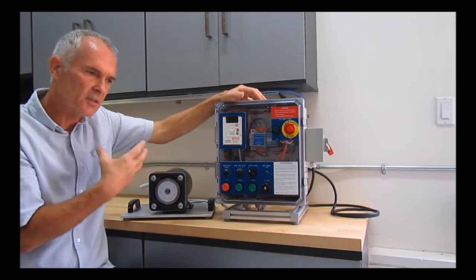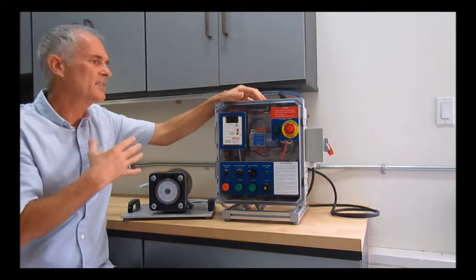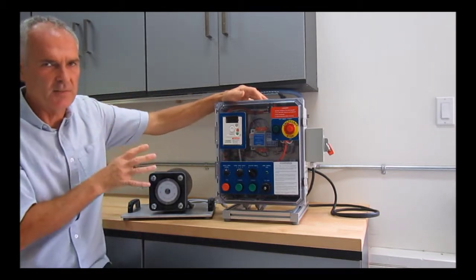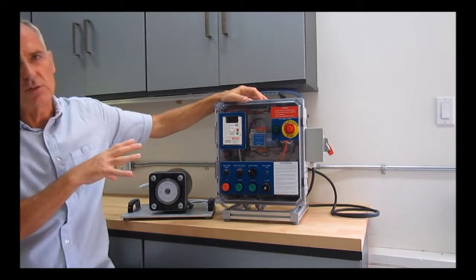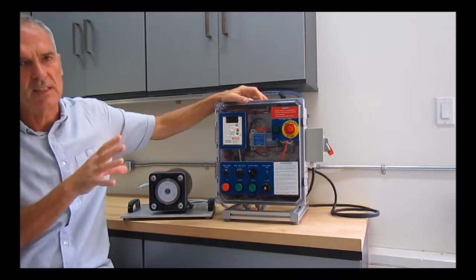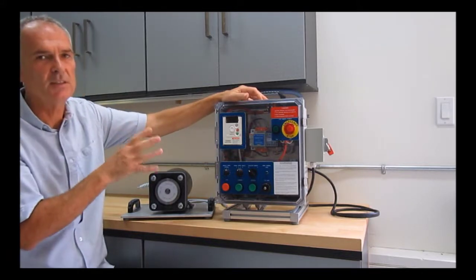The main operating modes - the first is pump mode, which is a variable torque mode for pump and fan. You can program it to that and it will save energy. If you're driving a pump it has a variable torque characteristic to it, so it would be very beneficial to set that parameter in motor control.